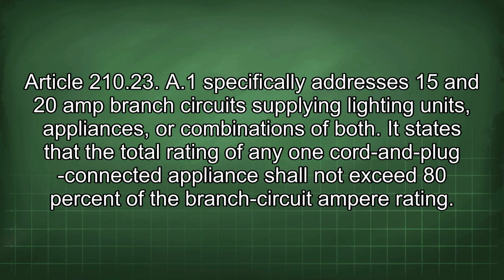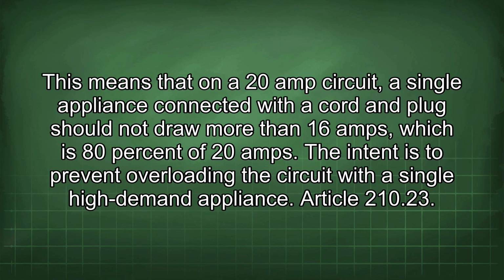Article 210.23 A1 specifically addresses 15 and 20 amp branch circuits supplying lighting units, appliances, or combinations of both. It states that the total rating of any one cord and plug connected appliance shall not exceed 80% of the branch circuit ampere rating. This means that on a 20 amp circuit, a single appliance connected with a cord and plug should not draw more than 16 amps, which is 80% of 20 amps. The intent is to prevent overloading the circuit with a single high-demand appliance.